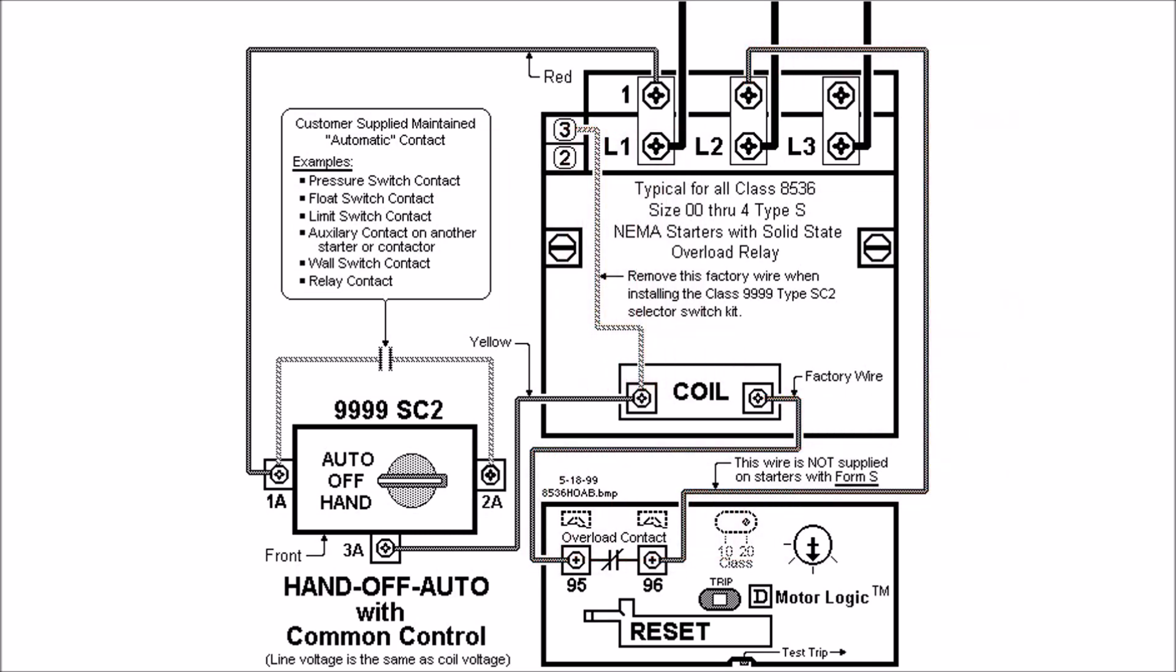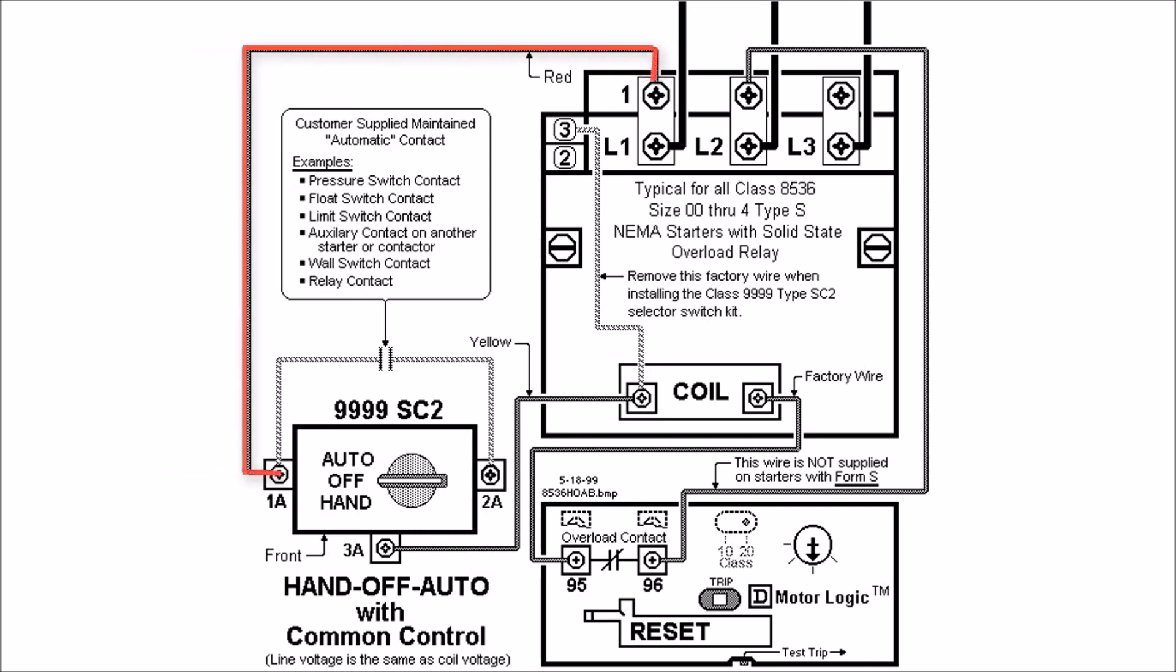The connection points to your HOA are a little bit different as far as your line voltage, where it comes in. 3A to the left-hand side of your coil is still there, so you'll still wire that. You'll see in the drawing on the screen that takeoff screw from behind terminal L1, it's actually labeled on the nameplate for terminal 1, will go to 1A of your handoff auto.